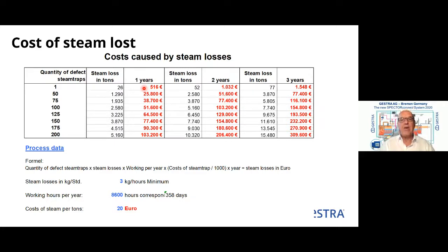And on average, we can say that maybe 10% of the steam traps in the plant have a problem with steam loss. So if you have 500 steam traps, then you have 50 steam traps which give you a problem after 1 year. And this means 50 steam traps are already 25,000 euro of loss of steam in the first year. And here we can see how important it is to make an annual check of your steam traps, whether they work correctly or have a problem.